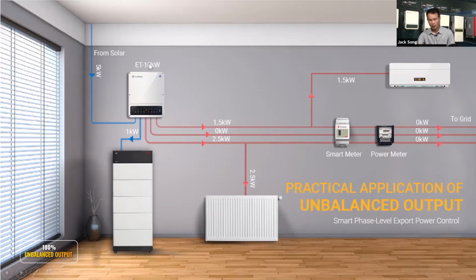Here we can see the unbalanced output function. For example, on the second phase we did not connect any loads, so there's no power consumption, but on the first and third phases we have load power. With the unbalanced function, the second phase does not have to export power, and its power is shared to the first and third phases inside the inverter, before the power meter of the house.